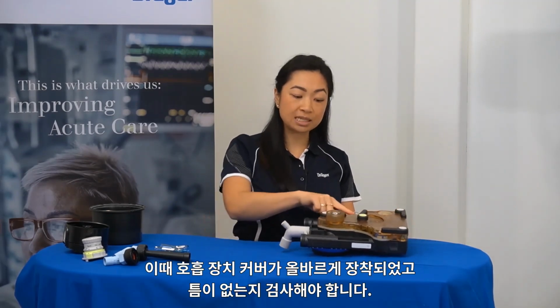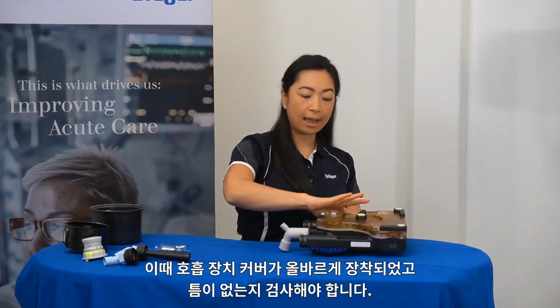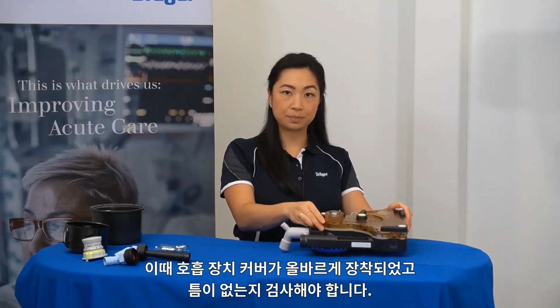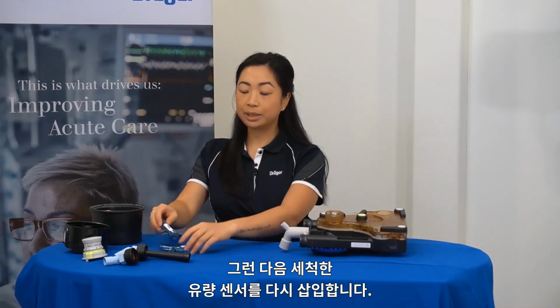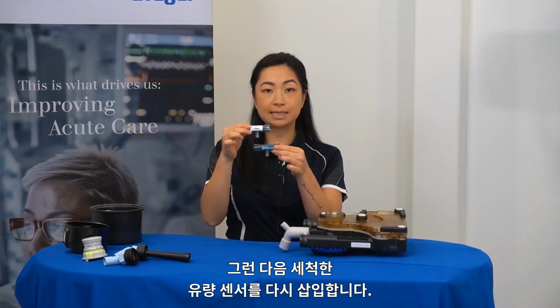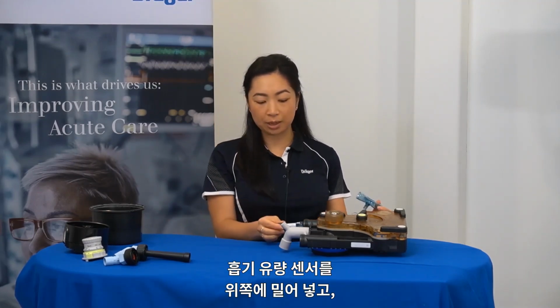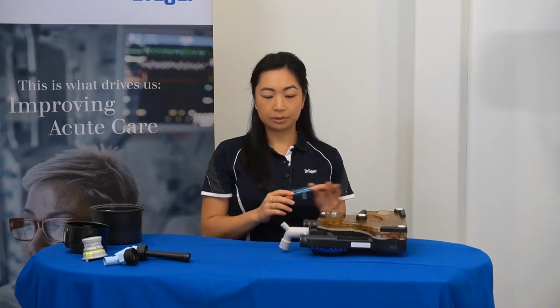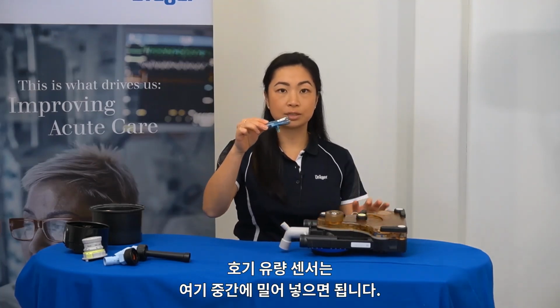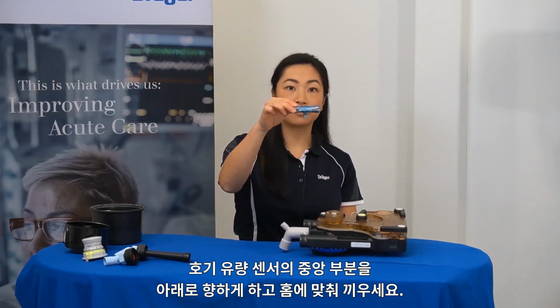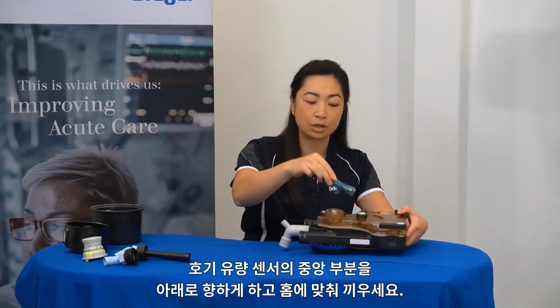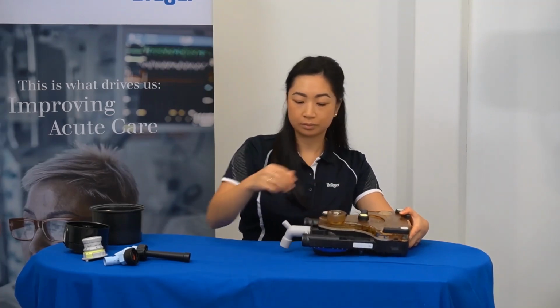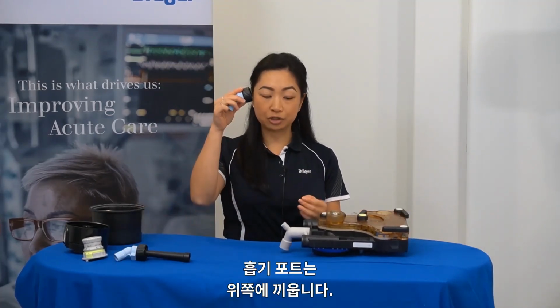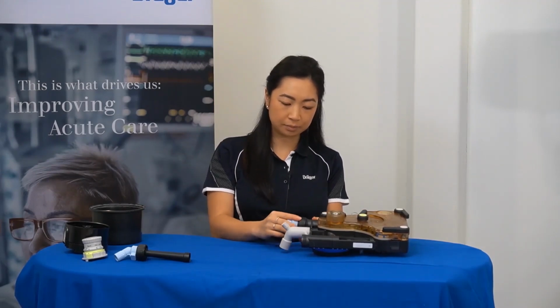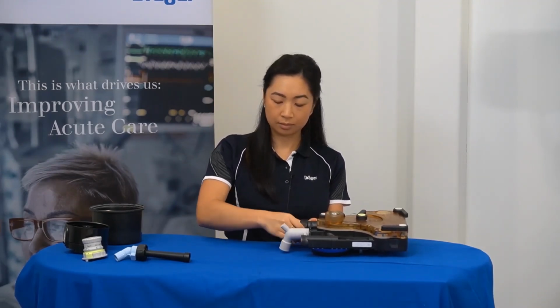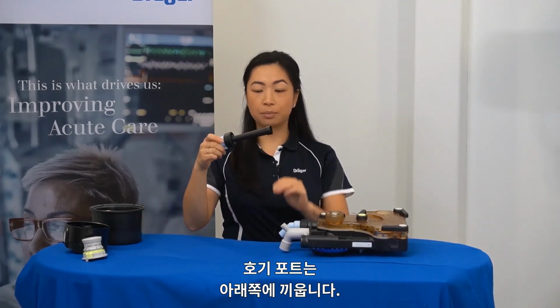At this point, you should inspect that the breathing system cover is fitted correctly and there are no gaps. Following that, your clean flow sensors can be reinserted. The inspiratory one by sliding it in at the top, and the expiratory one goes in the middle, ensuring that the middle of the flow sensor is pointing downwards into the notch. Then the inspiratory port at the top end, and the expiratory port in the bottom one.